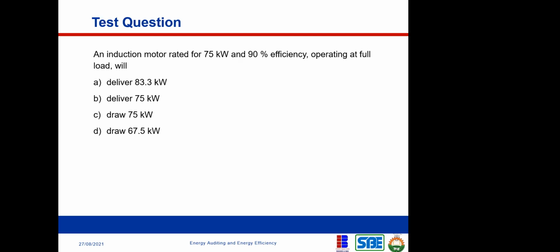So here's a test question. I want us to answer this. I don't think it even requires calculation; it requires our critical thinking. An induction motor rated for 75 kilowatts and 90% efficiency, operating at full load, will do what? If you know the answer, unmute your mic and speak. The rated 75 kilowatts is kilowatt mechanical, and we have been told that it is operating at 90% efficiency.